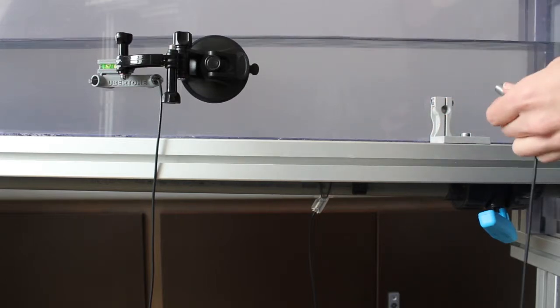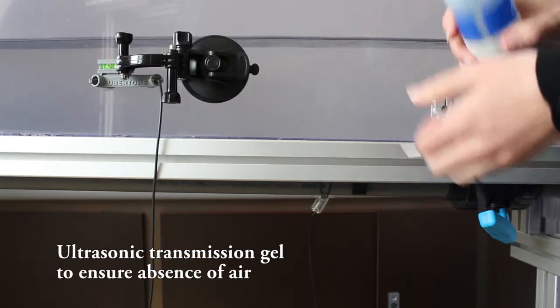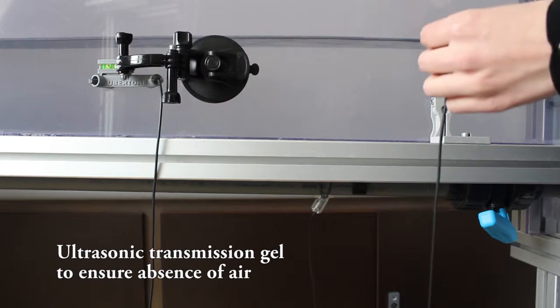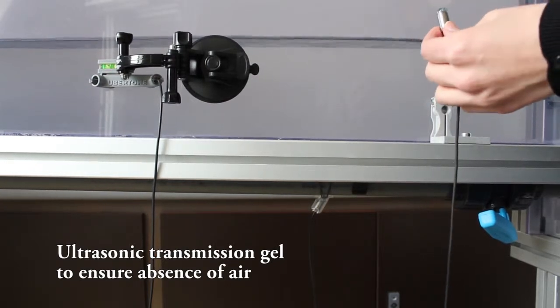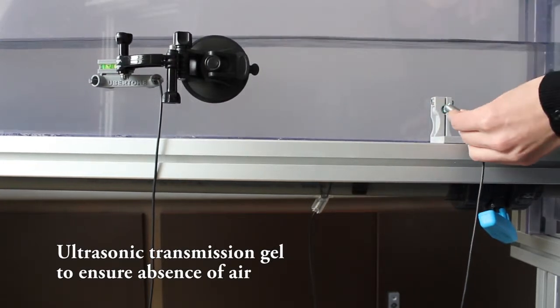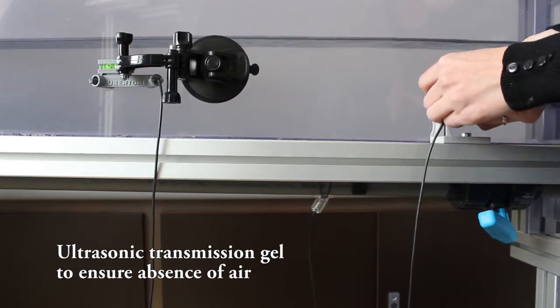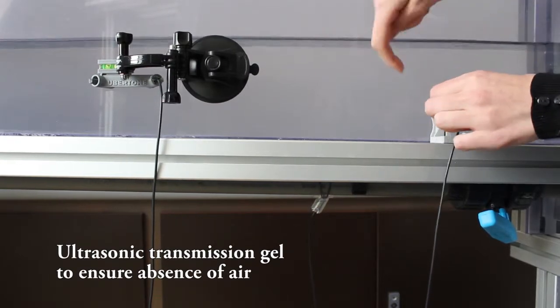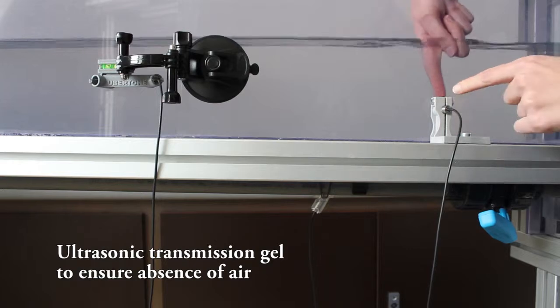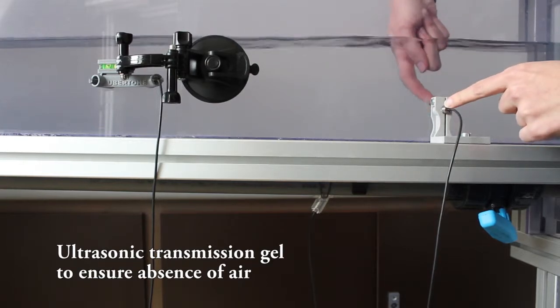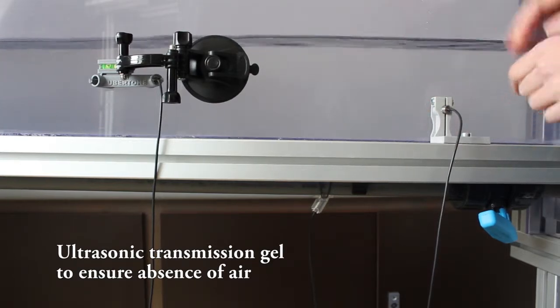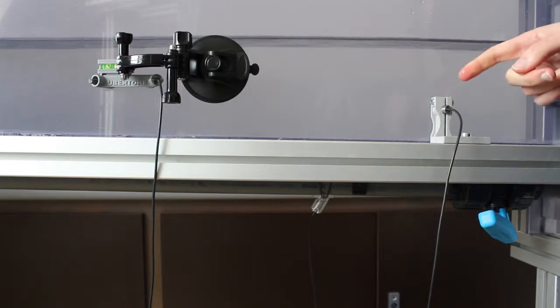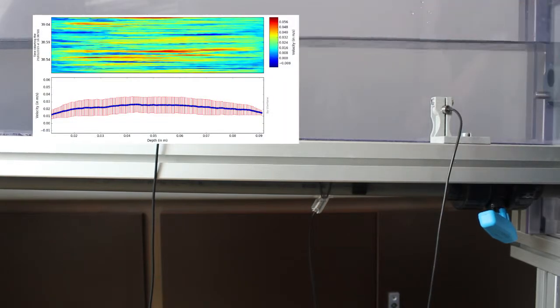to ensure the absence of air between the transducer and the wall. You need to put some gel. Like this. You will have to make sure that there are no bubbles between the transducer and the wall. Measured velocities with this holder look like this.